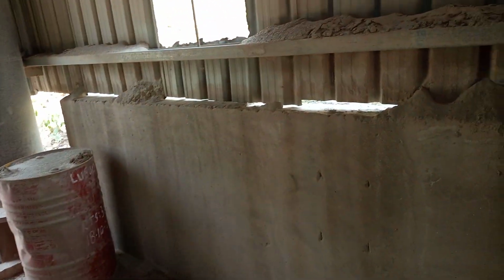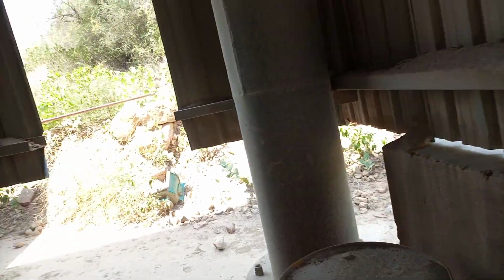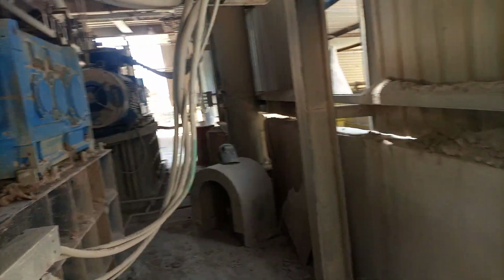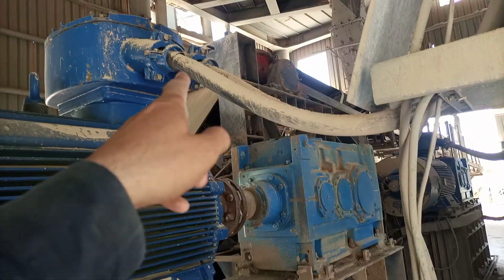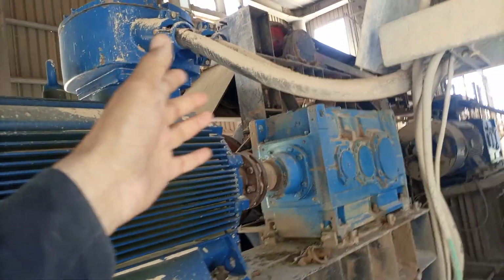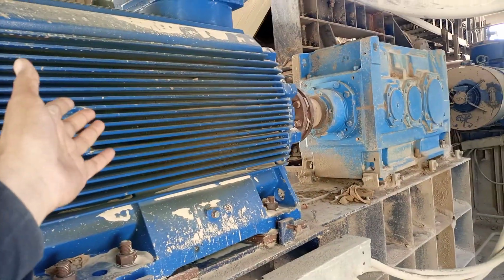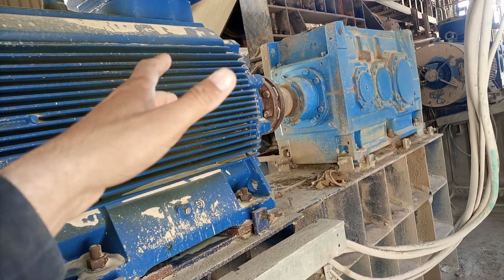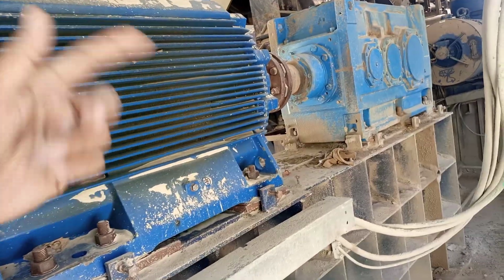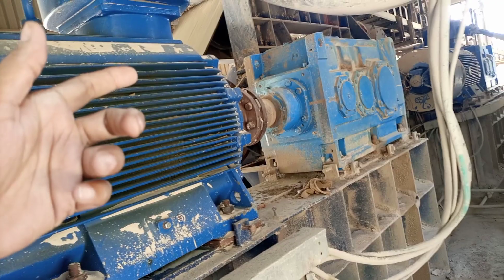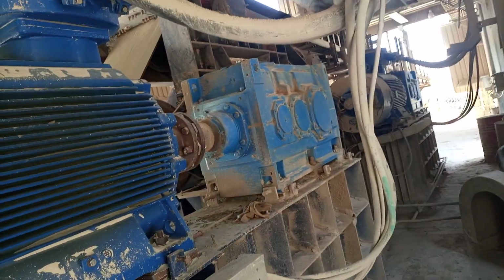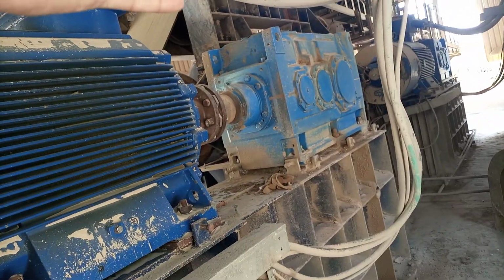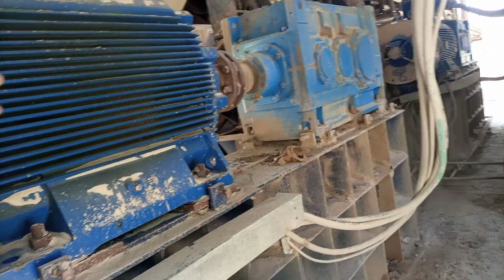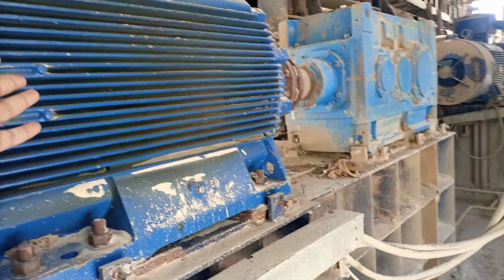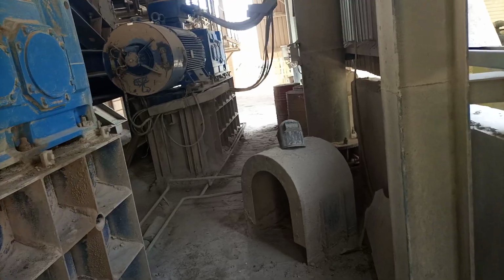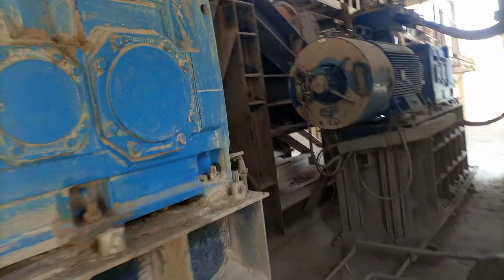Now I'm taking you to the other side of the system. Here you will see these are the two cables which are supplying power. Initially these cables supply power to the motor, and first the system is run by these motors. As the system comes to run, the belt conveyor also comes to run under the load, and under the load these motors are overdriven, becoming generators, and they supply power back to the line.